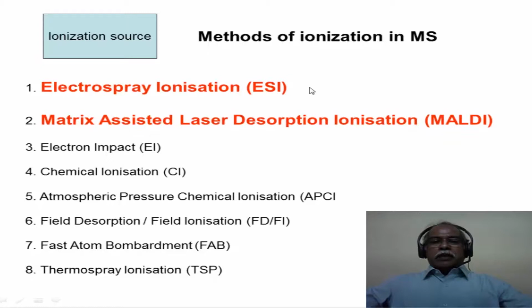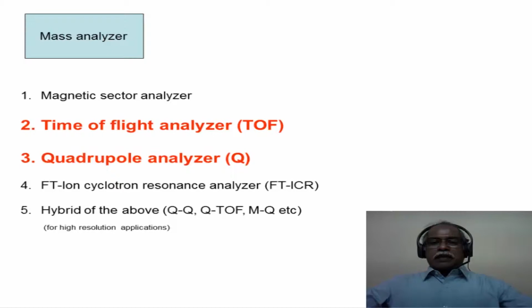So we will consider first the electrospray ionization mass spectrometry, the basic principle behind it in combination with the quadrupole analyzer. Typically, electrospray ionization with the quadrupole analyzer and the time of flight analyzer, what we call the QTOF ESI, is a standard combination, whereas in the case of MALDI, TOF is the standard combination, where MALDI is the ionization methodology and the time of flight analyzer is the mass analyzer.